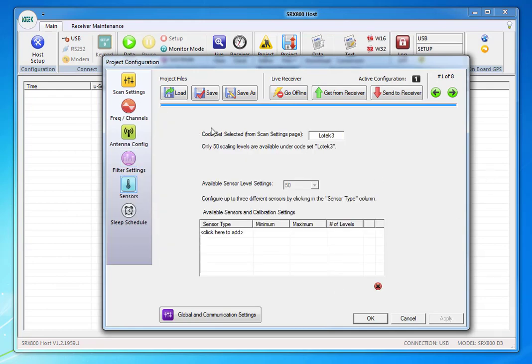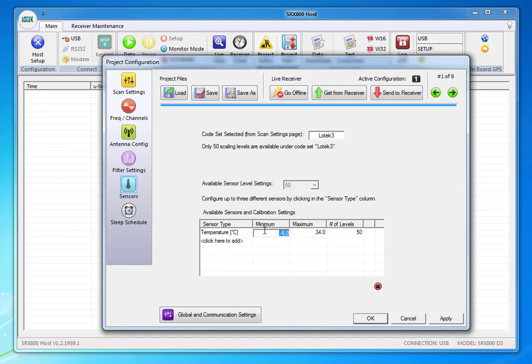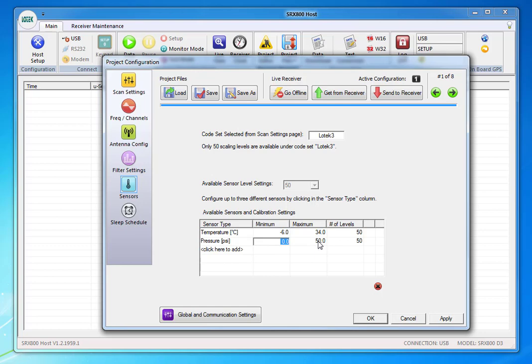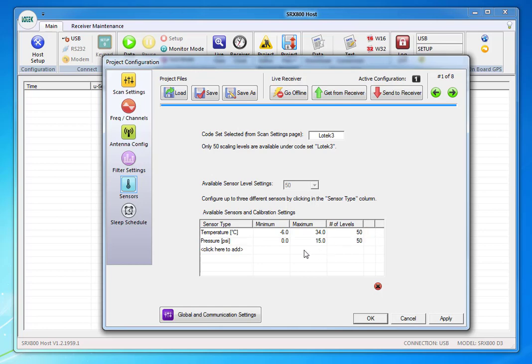It's going to say Lotek3 and then I'm going to add my temperature first. It's going to set a maximum and a minimum minus six and 34, and there's 50 levels. Then I'm going to select my pressure and this is when it really depends on what kind of pressure sensor. If you have a maximum of 50 psi, then you would leave it as such. But if it's 15 psi, just key in 15 and it'll give you 15 psi broken into 50 increments.